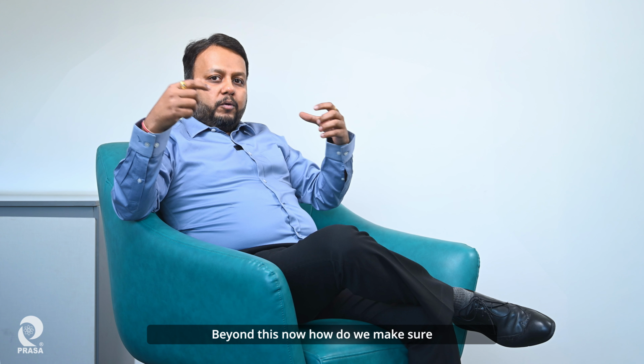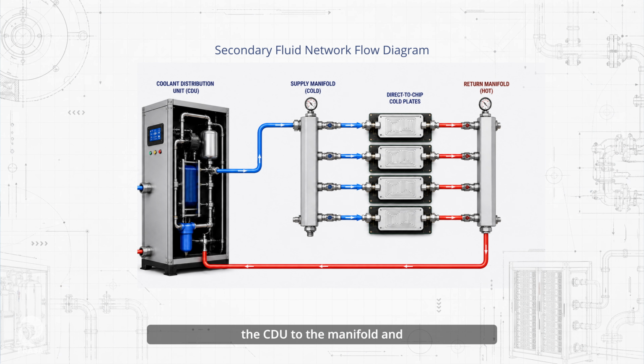Beyond this, how do we make sure the liquid moves from the CDU to the manifold, and the manifold to the cold plate, and back from the cold plate to the manifold and manifold to the CDU? That we call the technology water loops, also known as SFN, secondary fluid networks.